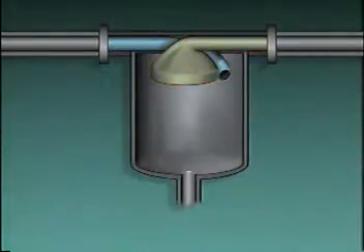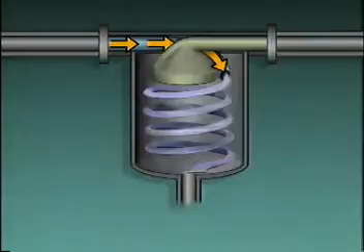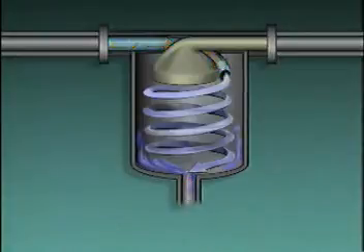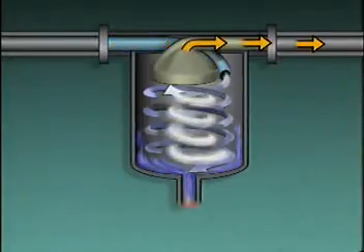As moist gas enters the de-mister, it begins spinning. Because liquids are heavier than gases, centrifugal force causes liquid to separate from the gas and hit the shell. The liquid runs down the shell and out through the liquid outlet. The gas enters the collector and leaves through the gas outlet.